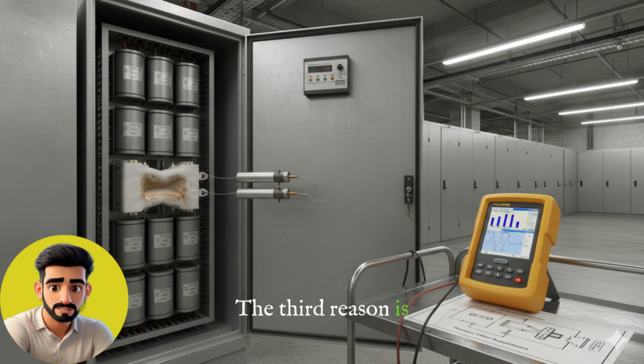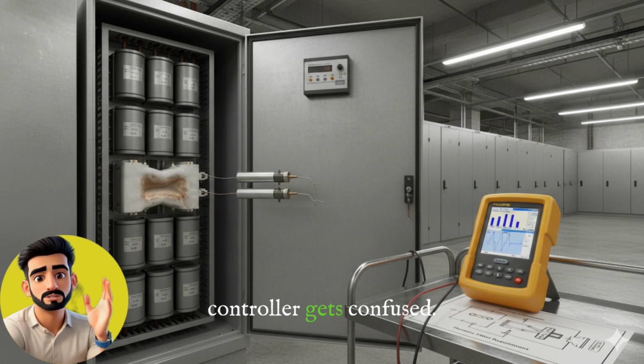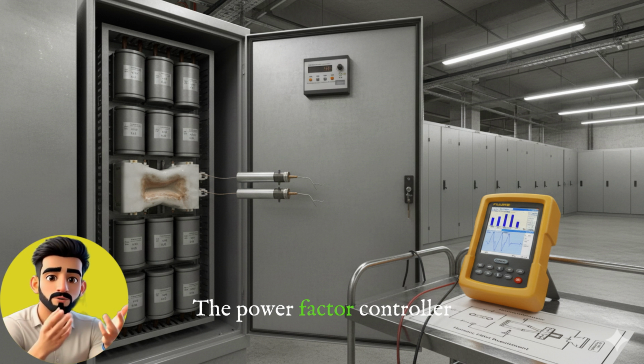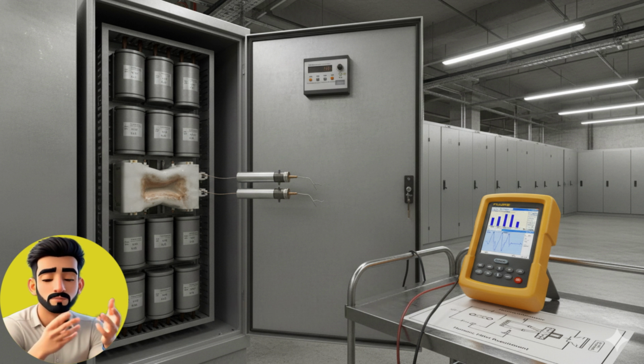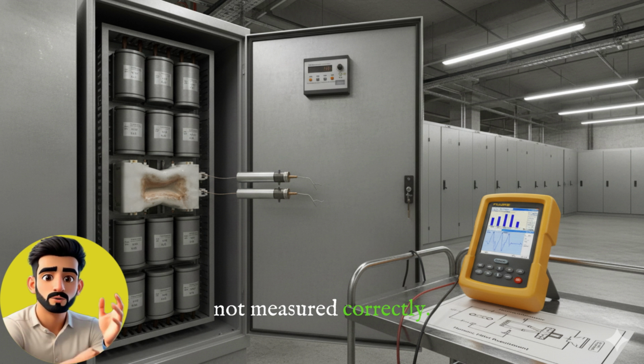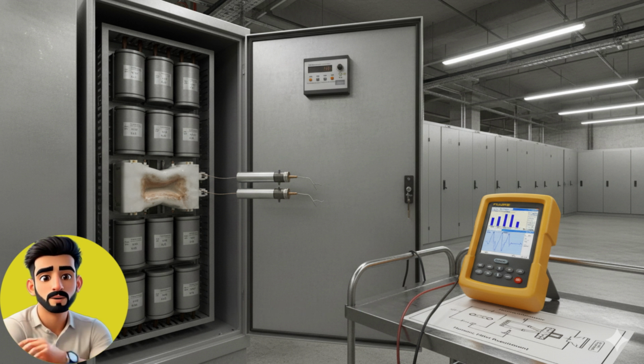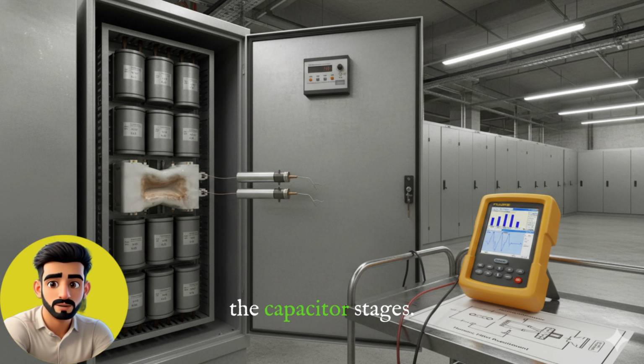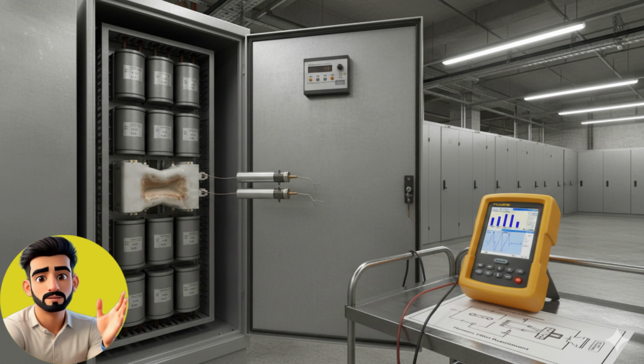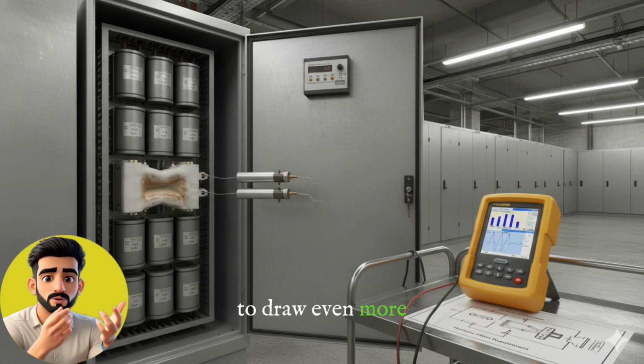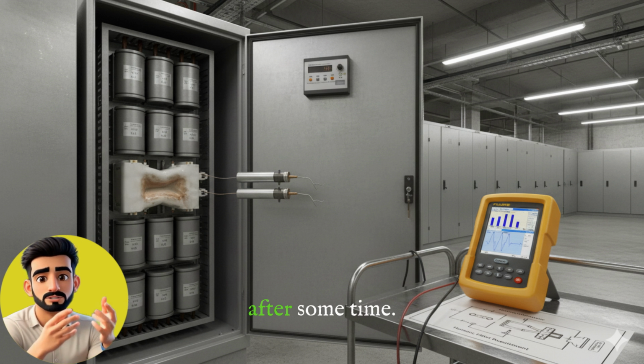The third reason is that the power factor controller gets confused. The power factor controller measures the angle between voltage and current. But in a harmonic waveform, the angle is not measured correctly. The controller thinks the power factor is low and it switches on the capacitor stages. This capacitor stage turns on at the wrong time when the voltage is distorted. This causes the capacitor to draw even more current and it fails after some time.